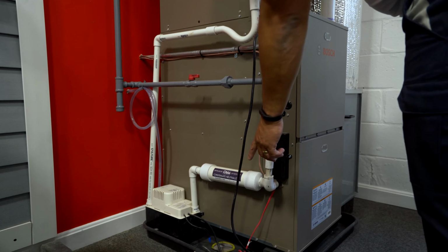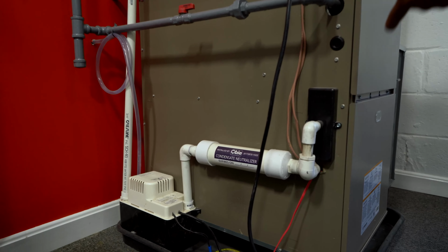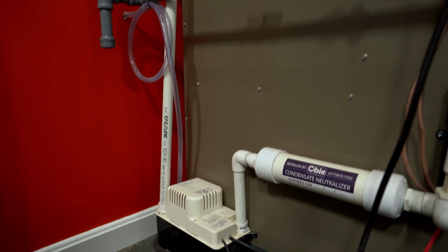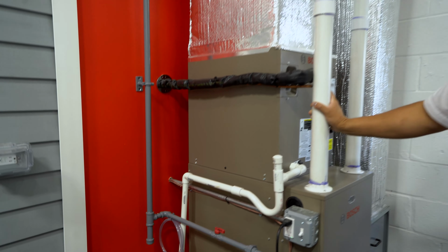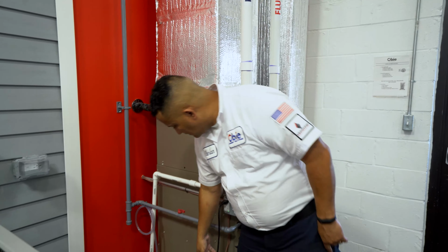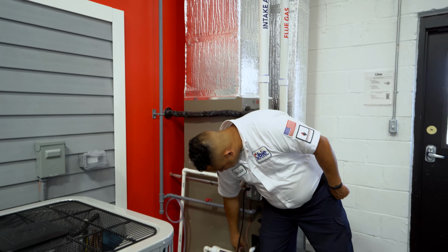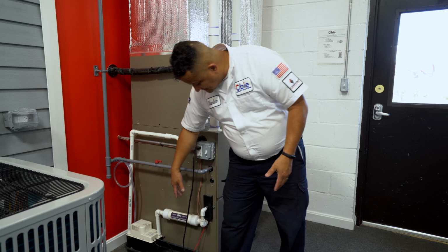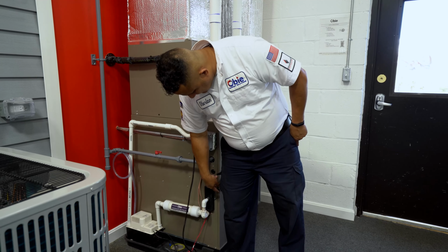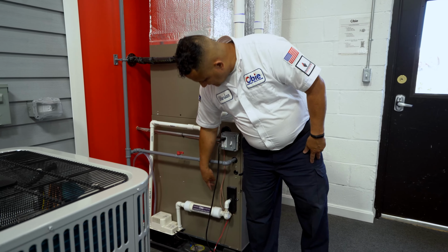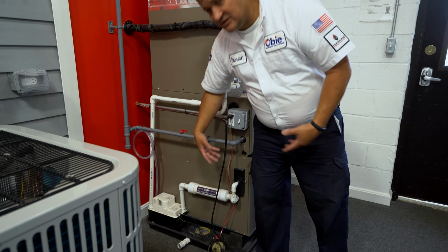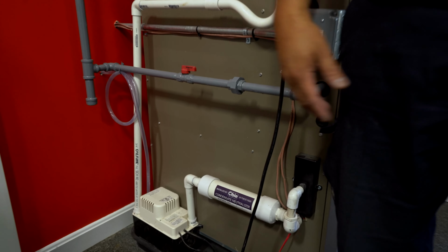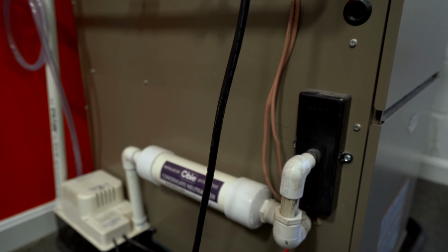And the same thing with the gas furnace. This is a 96% two-stage gas furnace, and this furnace creates condensation while you're heating during the winter time. So that's why the pipe you see comes out in here from the gas furnace and goes directly into the condensate pump. Another thing is, the condensation produced by the gas furnace is very acidic, so that's why we have the condensate neutralizer. That is just to make this condensation more basic before it goes into the sewer line or even goes outside.